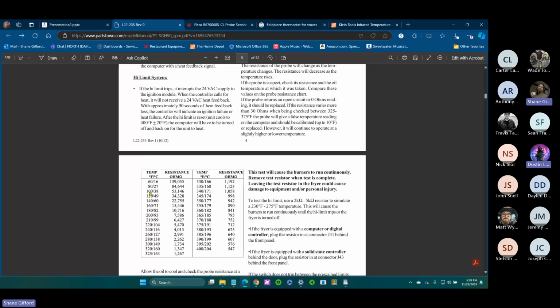There's nothing wrong if you don't have something that goes up to 700 degrees. Just shut it down for a while. Yep. And this shows you all these up to 400 degrees. So hypothetically, you could disconnect it from the controller, test your ohms, and it'll get you ballpark somewhat close. These don't necessarily fail to a specific outrageous number like Manitowoc sensors and stuff do.